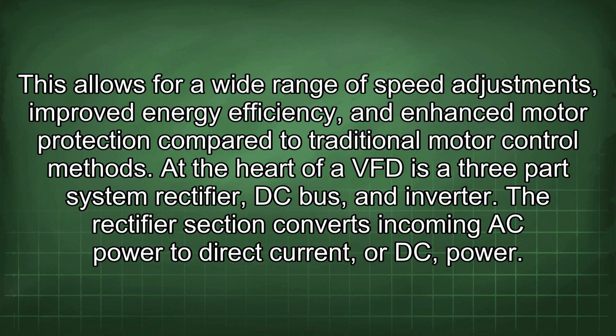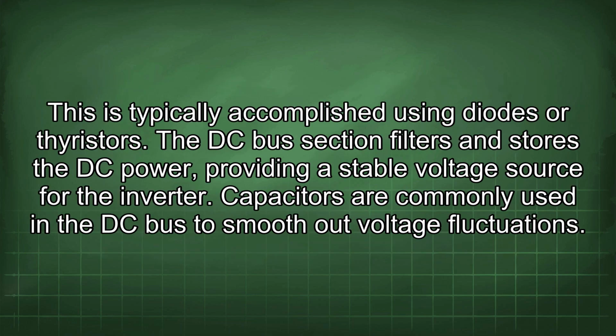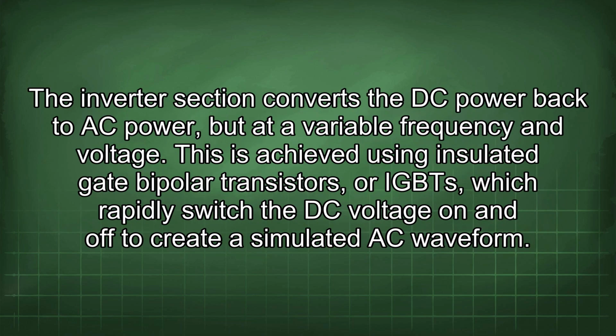The rectifier section converts incoming AC power to direct current, or DC, power. This is typically accomplished using diodes or thyristors. The DC bus section filters and stores the DC power, providing a stable voltage source for the inverter. Capacitors are commonly used in the DC bus to smooth out voltage fluctuations. The inverter section converts the DC power back to AC power, but at a variable frequency and voltage. This is achieved using insulated gate bipolar transistors, or IGBTs, which rapidly switch the DC voltage on and off to create a simulated AC waveform.